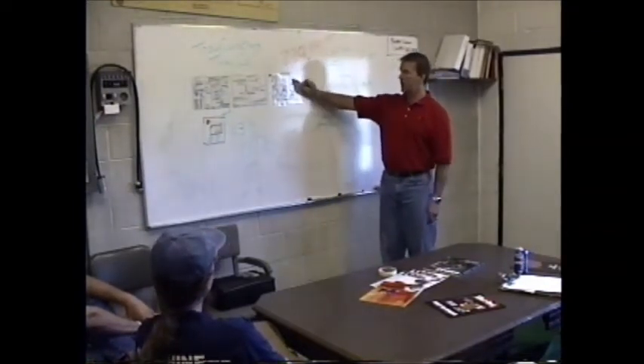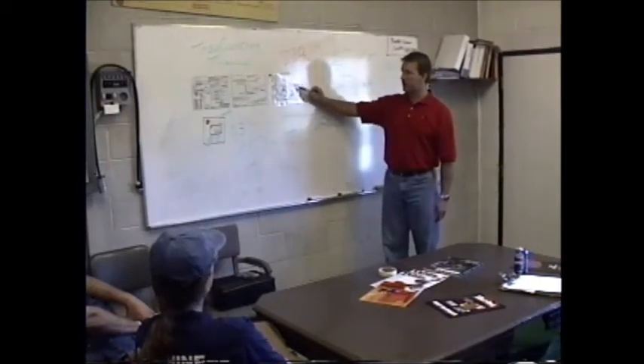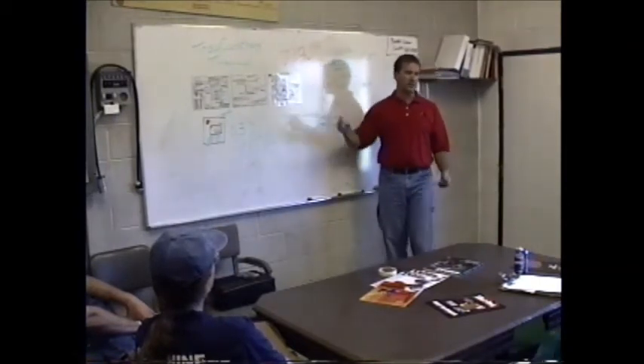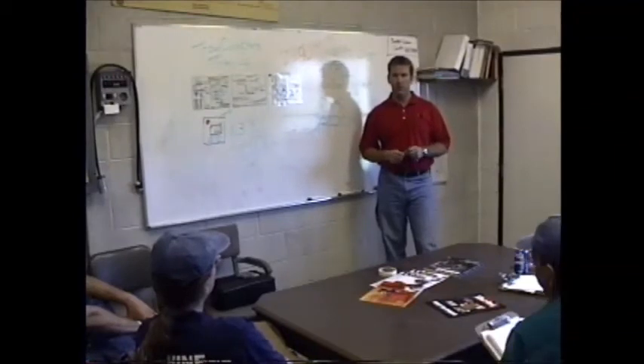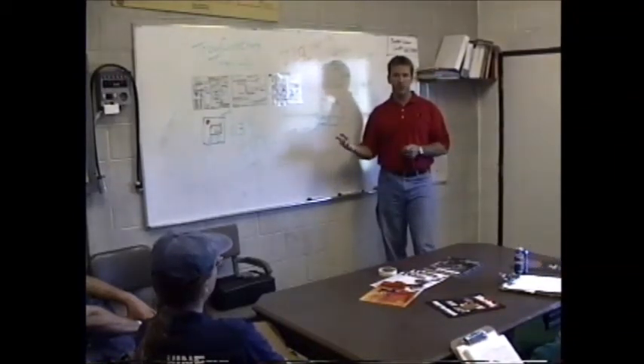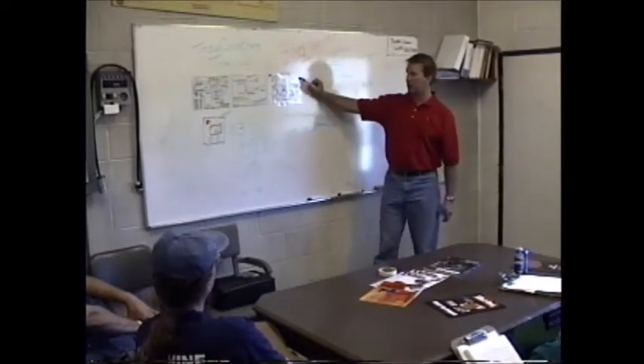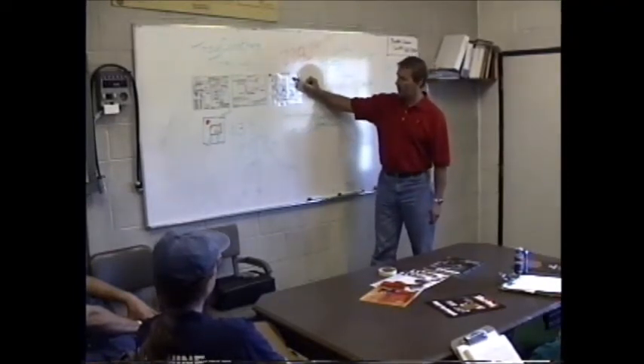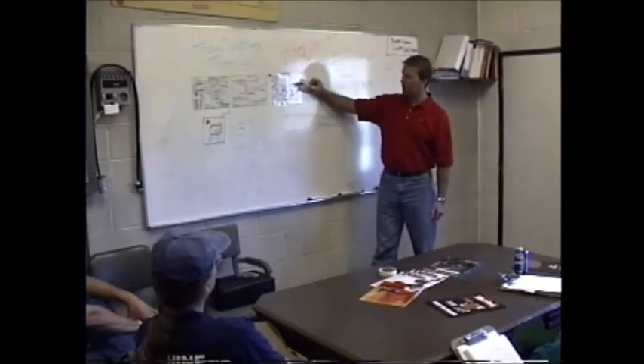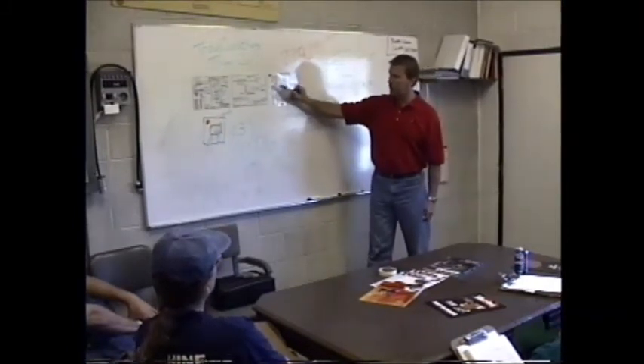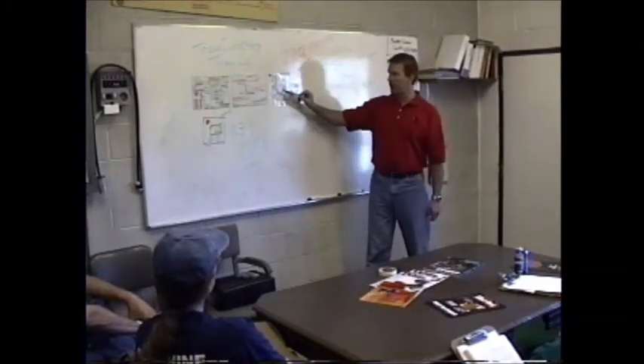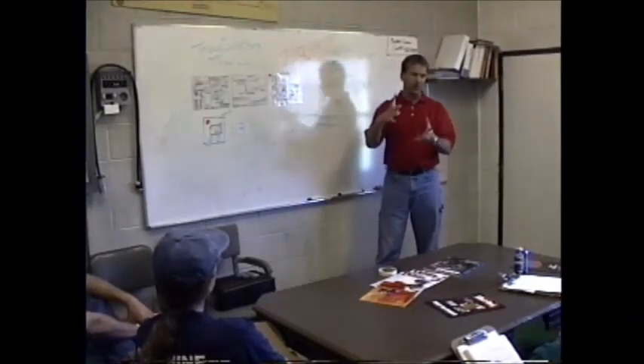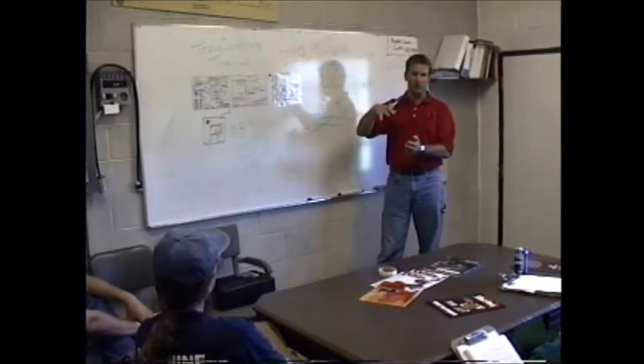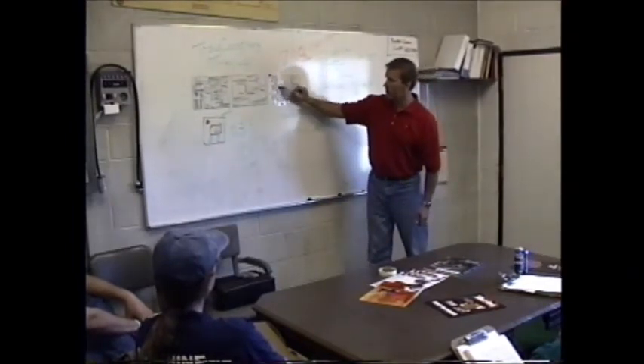It then opens the inlet valve. This air inlet valve that sits on top of the air compressor acts like the carburetor for the air compressor. Okay? If it needs to go faster or build more pressure, you bring in more gas, like through a carburetor. But in this case, we're bringing in more air. We bring in air through this carburetor or through this air inlet valve. It comes into the inlet of the compressor along with that oil, gets compressed, goes into this tank, builds up the pressure in that tank. But we're talking a very small tank here. This isn't a storage tank by any means. But it goes into this reservoir.